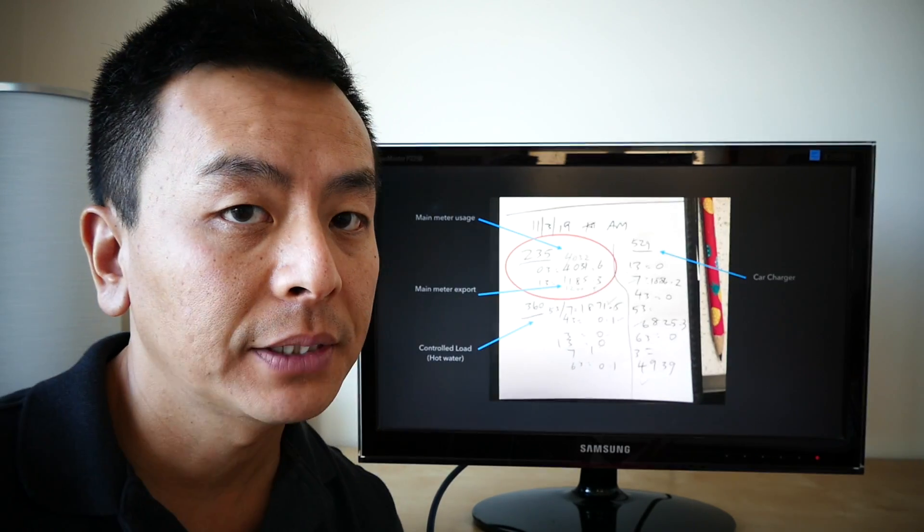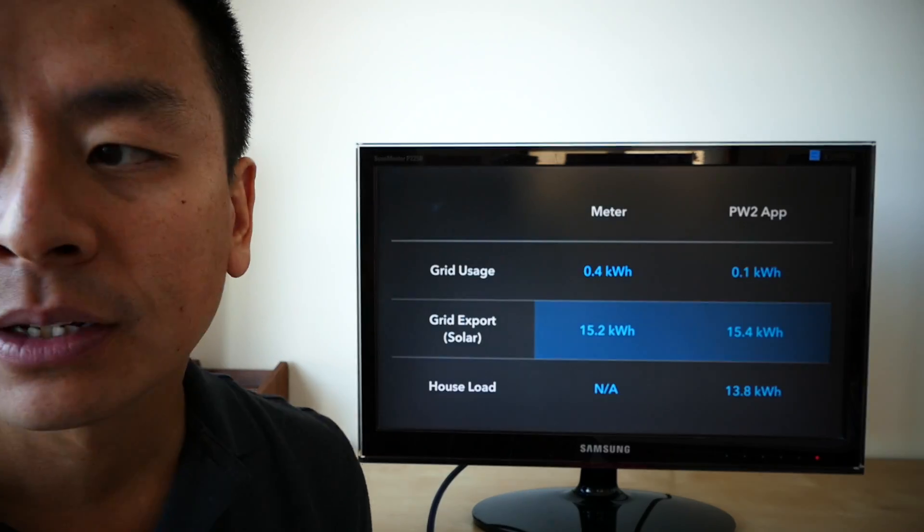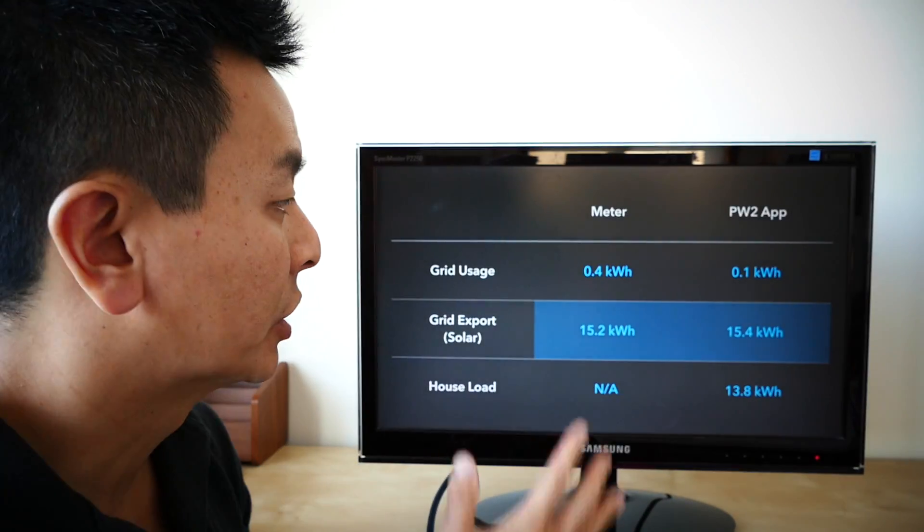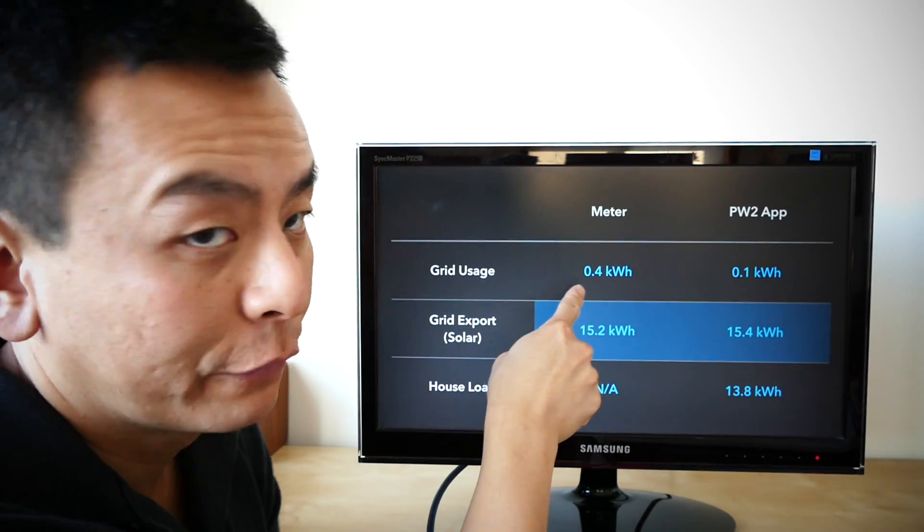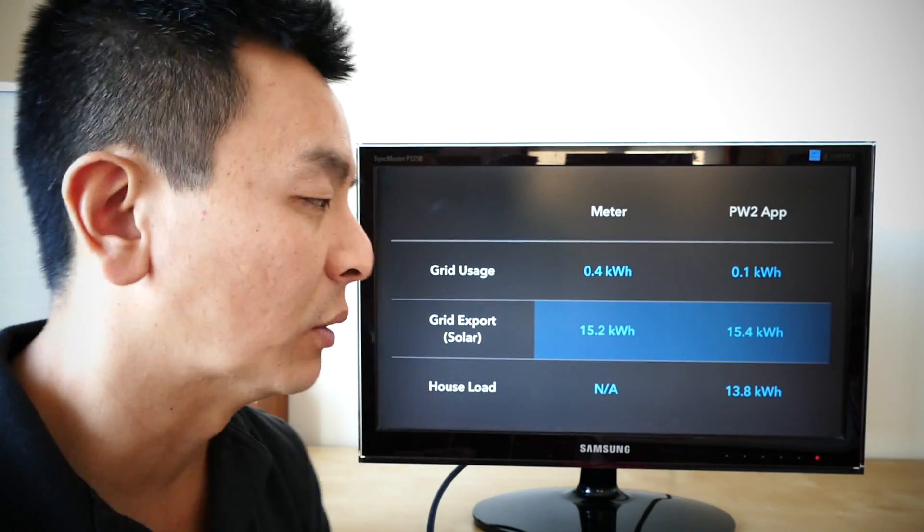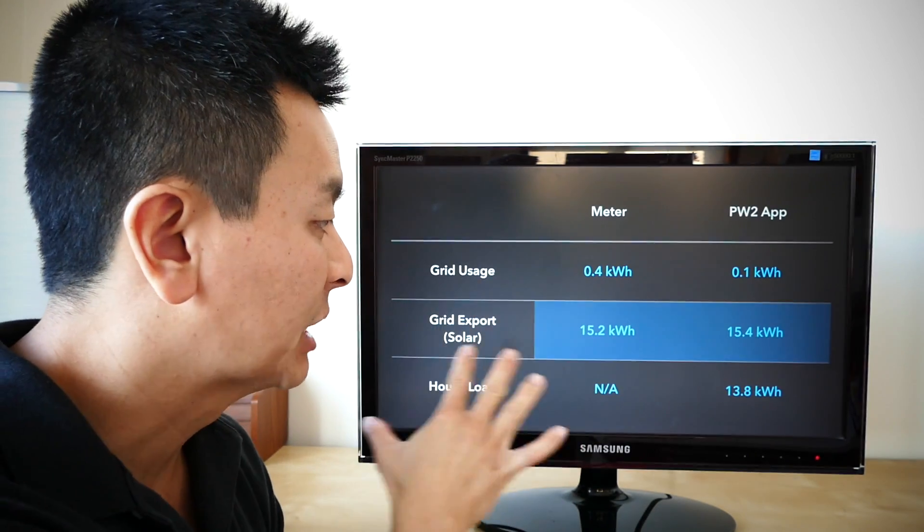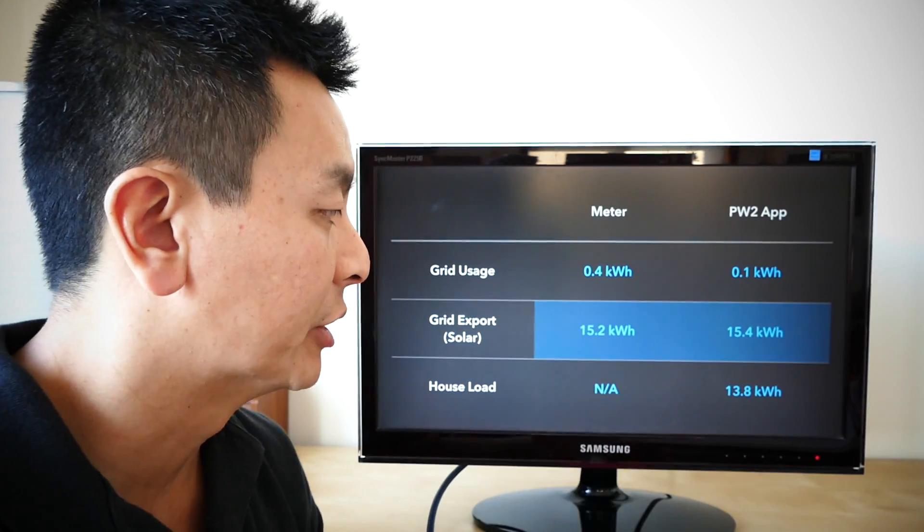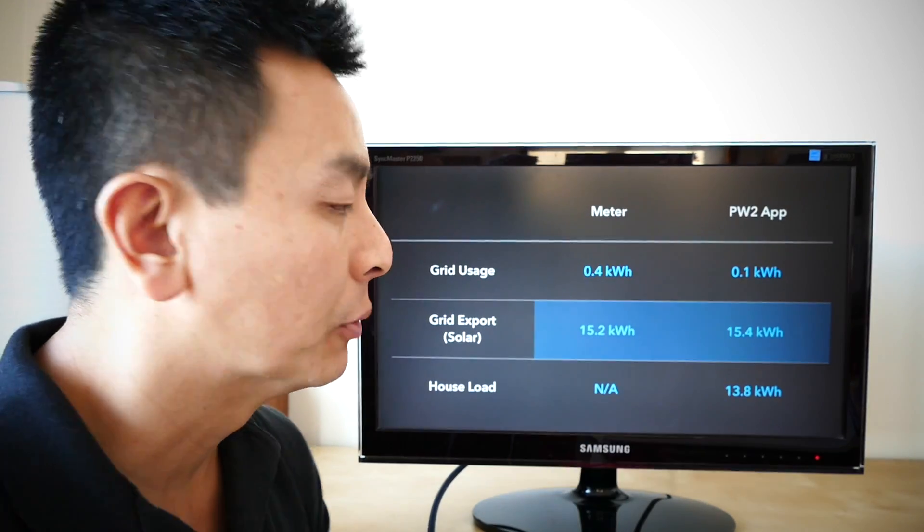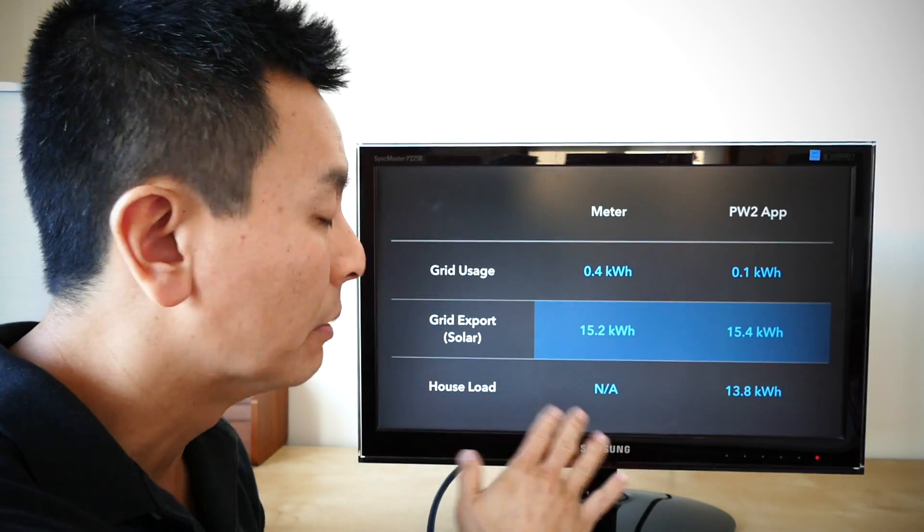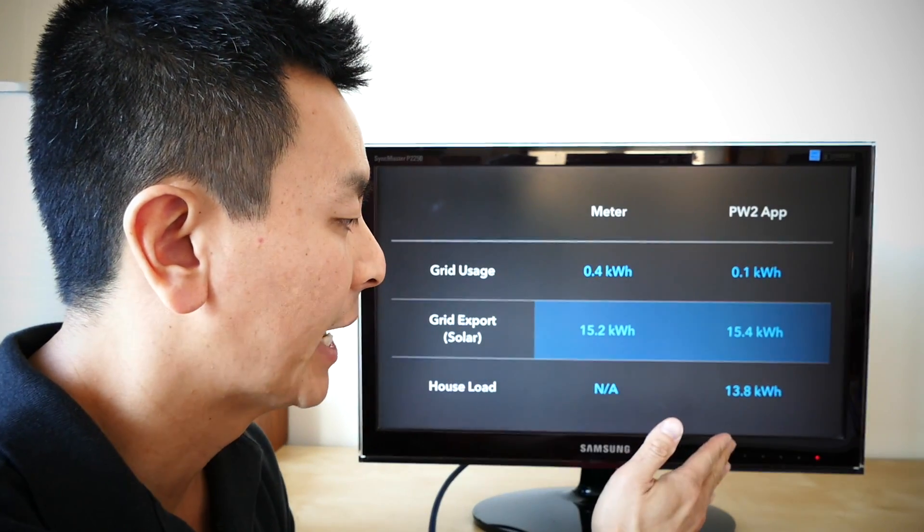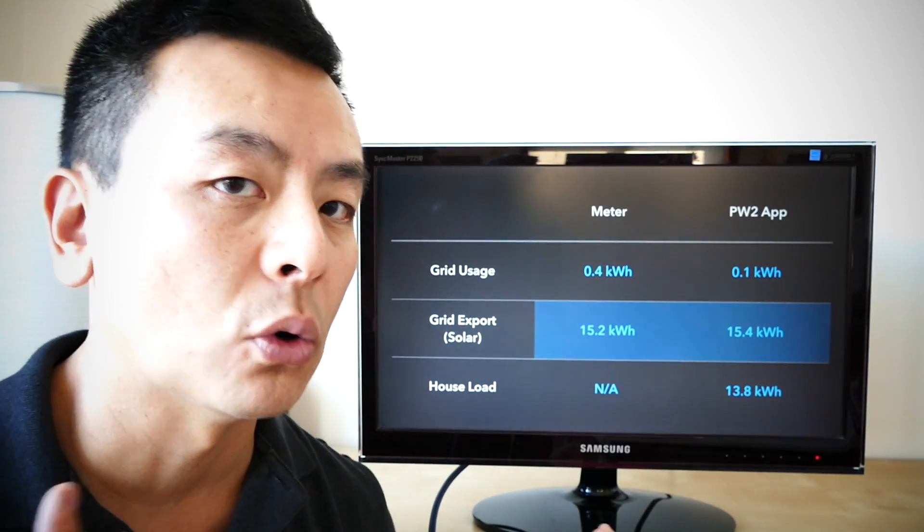So how does that match with what the app told me? Let's have a look at the next slide. So this is what it looks like when I compare the two. The meter grid usage, 0.4 kilowatt hours. The Powerwall 2 app told me it was 0.1 kilowatt hours. In terms of export, the meter told me the grid received 15.2 kilowatt hours. The app told me that we exported 15.4 kilowatt hours. In terms of load, the meter can't tell you that, but the app told me the house used 13.8 kilowatt hours.